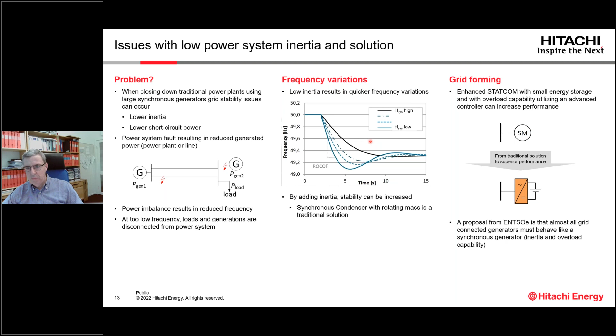And one way to reduce this frequency change is that we could add inertia. And one way to do it is to use a synchronous condenser, which has a rotating mass. But we believe that instead of a synchronous condenser, we should use an enhanced STATCOM. That is a STATCOM with a small energy storage and handles overload. And it has an advanced controller, of course, to increase the performance.